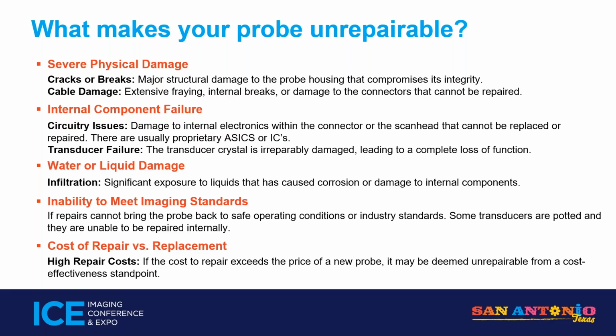Inability to meet imaging standards - I can't tell you how many probes I see in the field. I go in, turn on the machine, the probe comes up and it's got a dropout. I don't even have to do anything. It's got a big dropout, and they continue to use it. It's not only a problem for 2D image quality, but also a problem with Doppler noise.